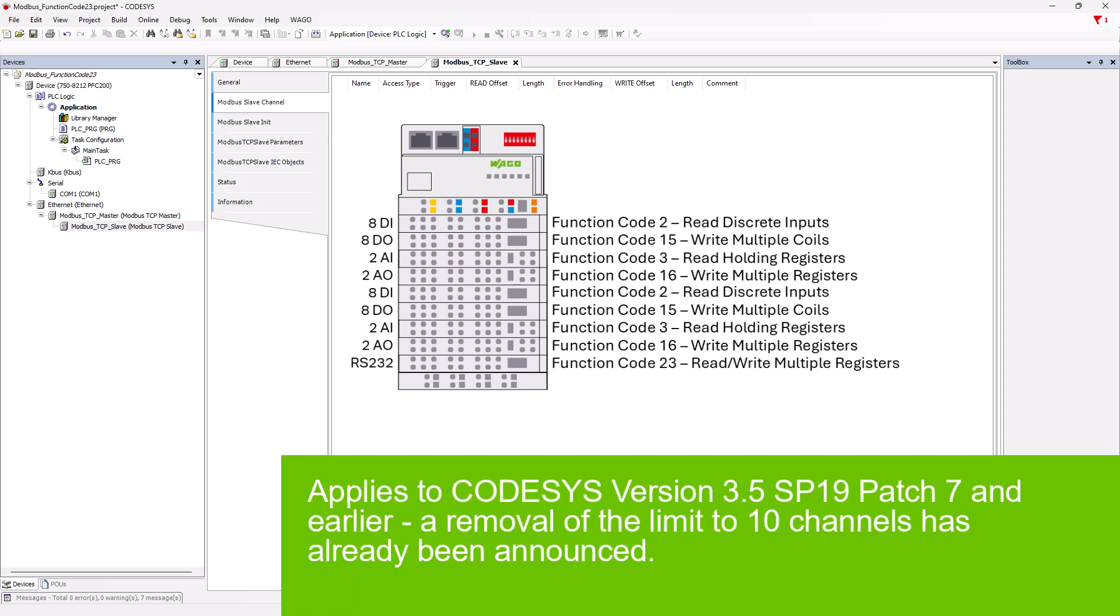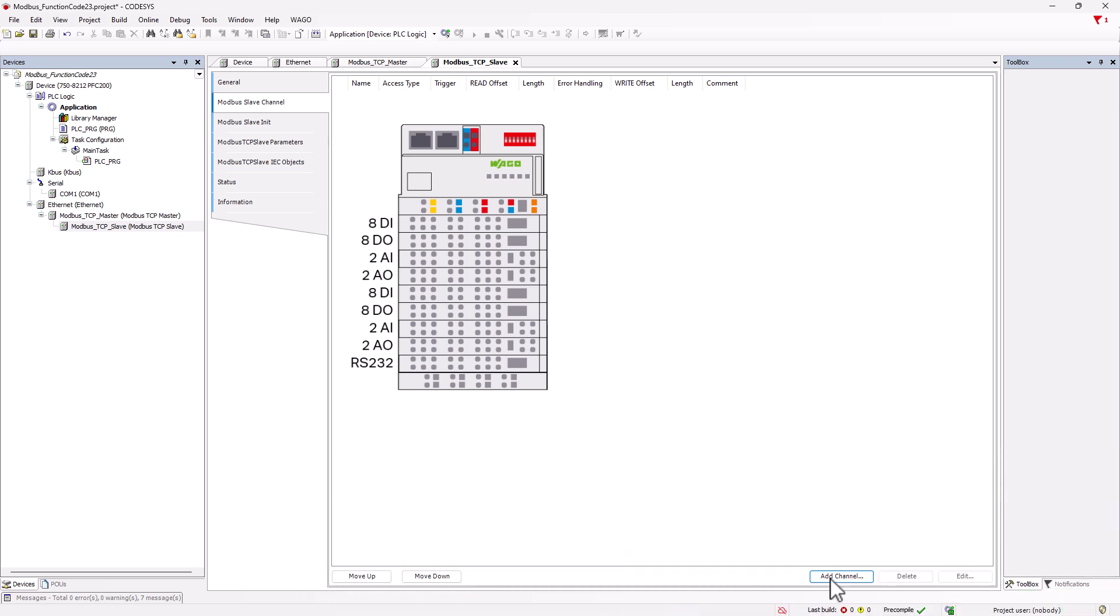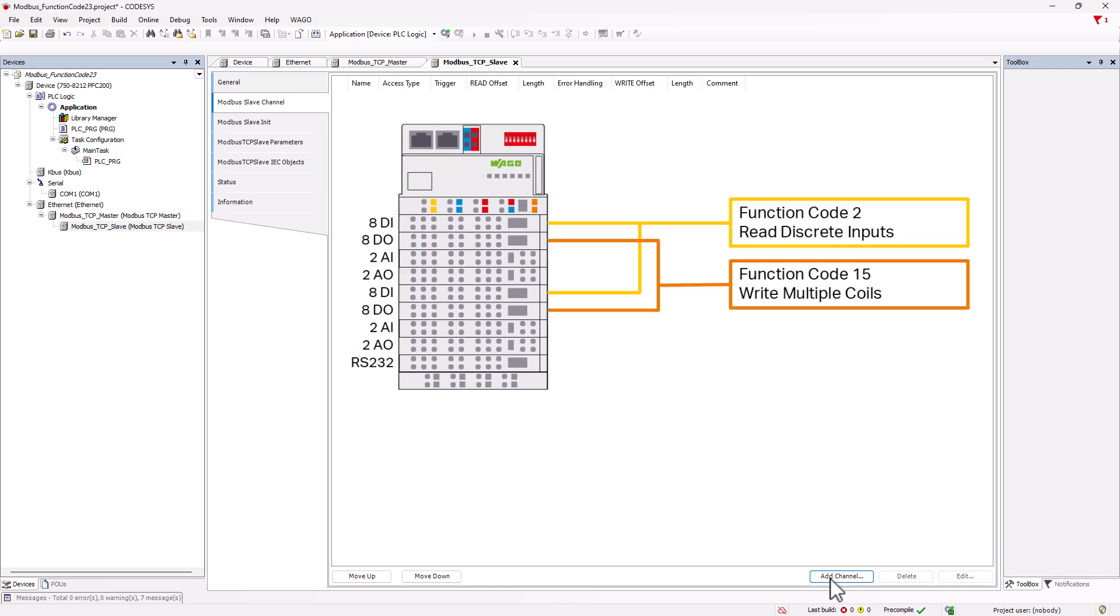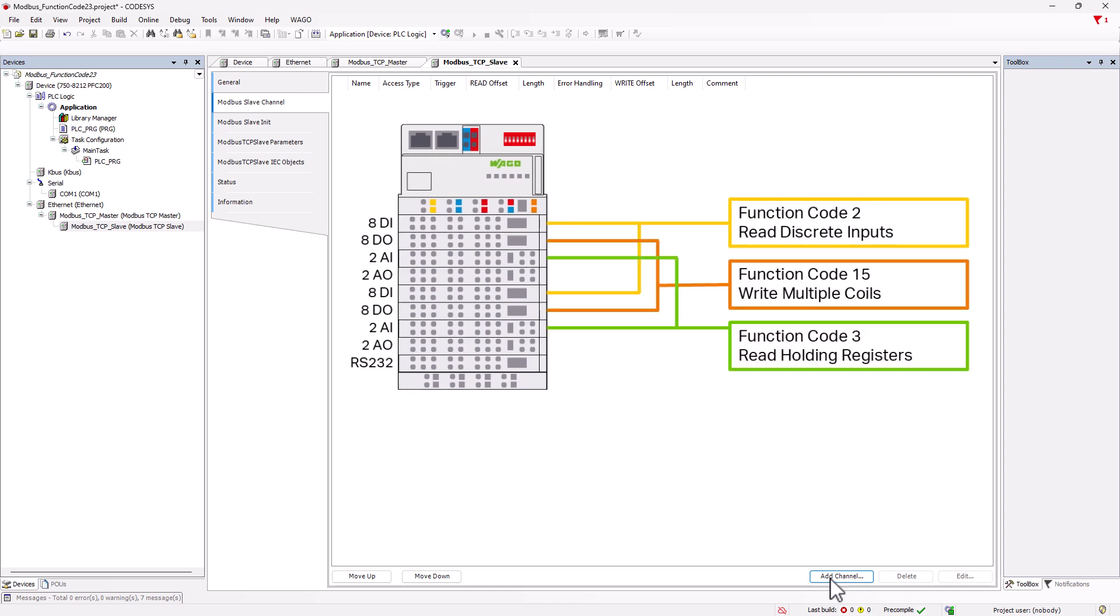Moreover, in CodeSys 3.5, the number of channels is limited to a maximum of 10. It can therefore be useful to consolidate channels. For example, you could group all digital inputs into one channel with function code 2, all digital outputs with function code 15, all analog inputs with function code 3, and all analog outputs with function code 16.